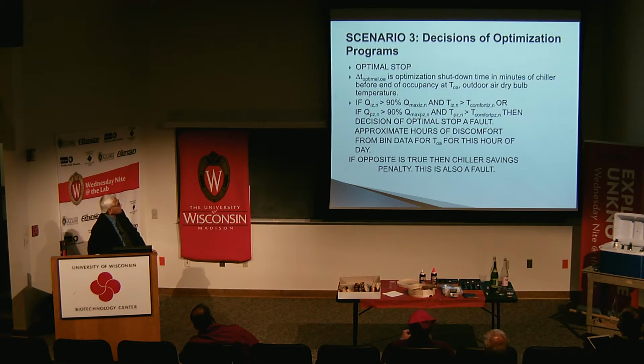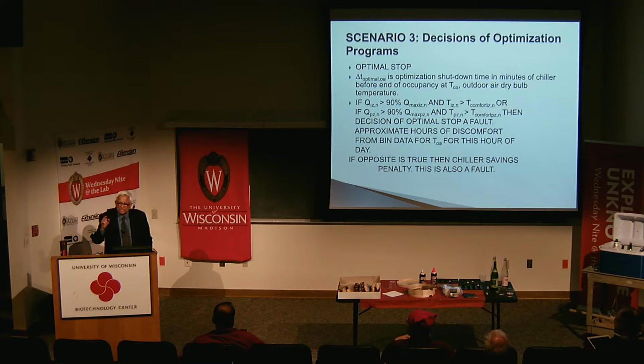Now, the decision of the optimization program. This is concerning the optimal stop I explained to you. If the optimal stop does not stop properly ahead of time, say the room temperature exceeds 78 degrees Fahrenheit, then you know that optimal stop has incurred a penalty. Maybe it has stopped too close to the optimal situation so that the temperature is increased. So if the temperature increases, you put a penalty on the optimal stop program.